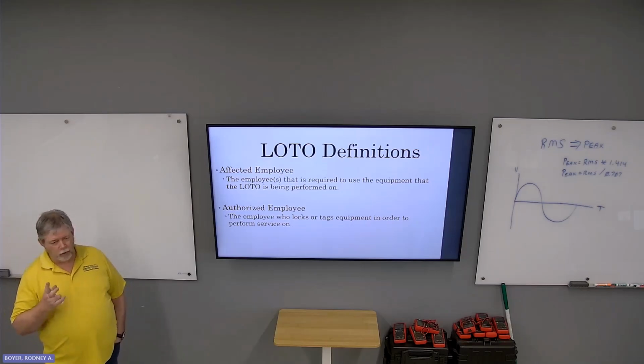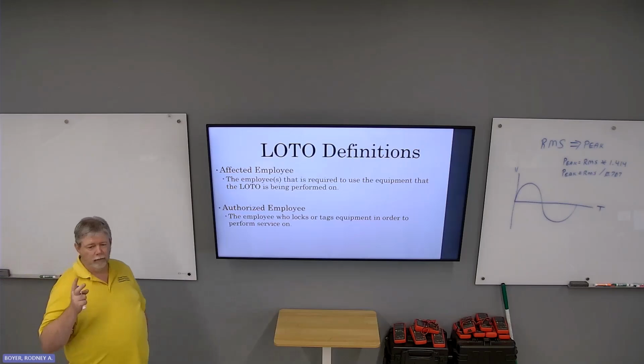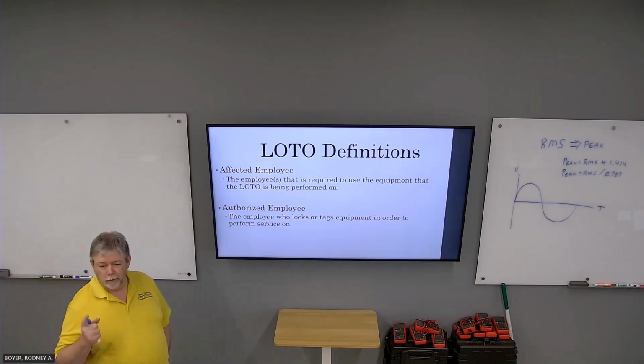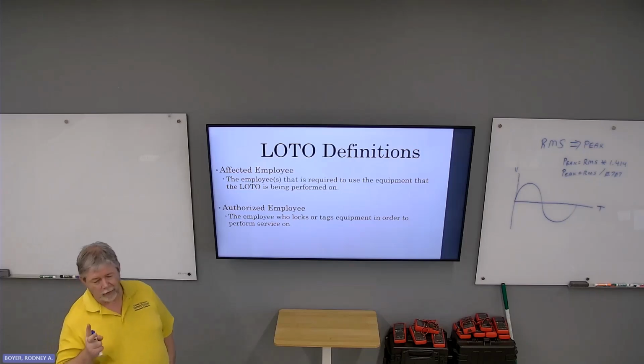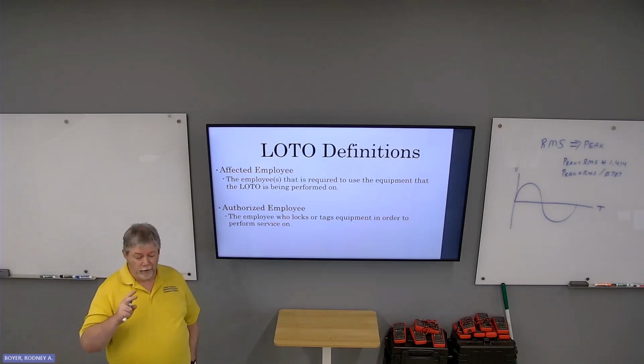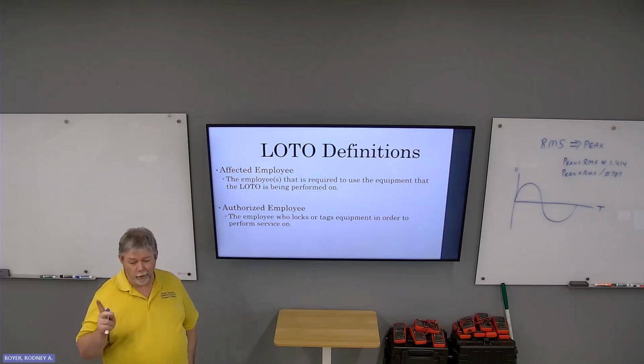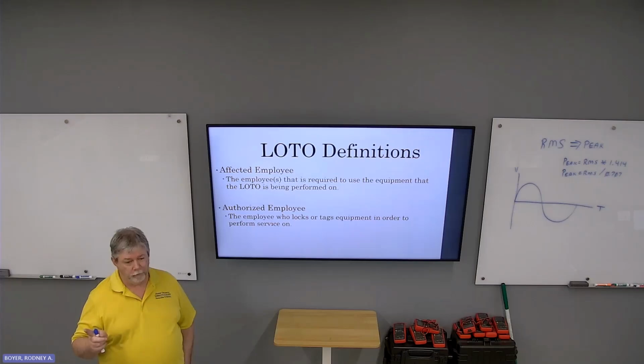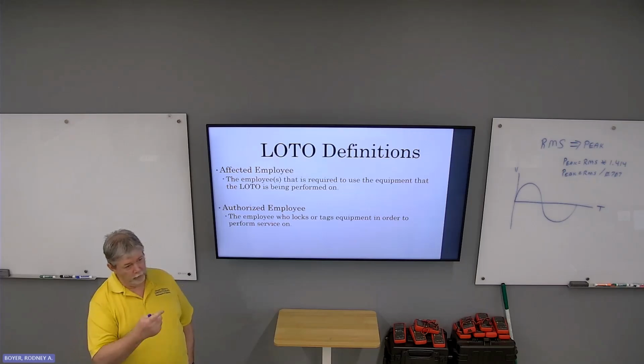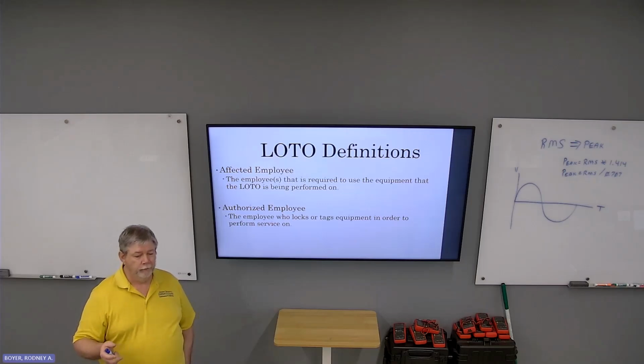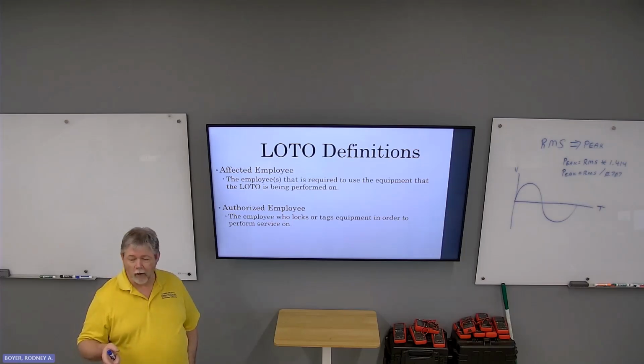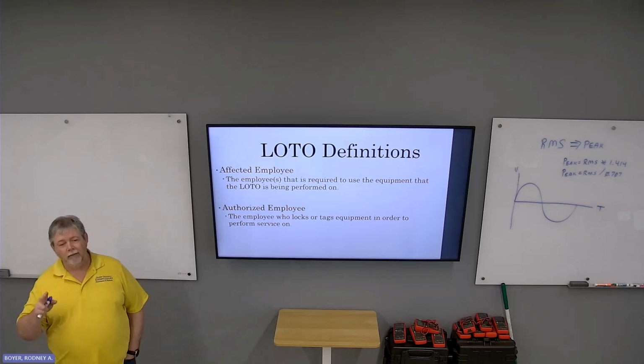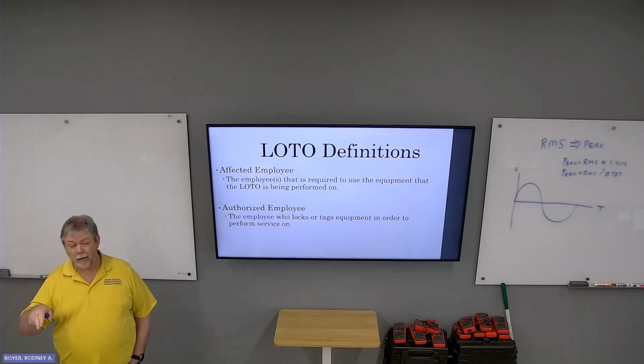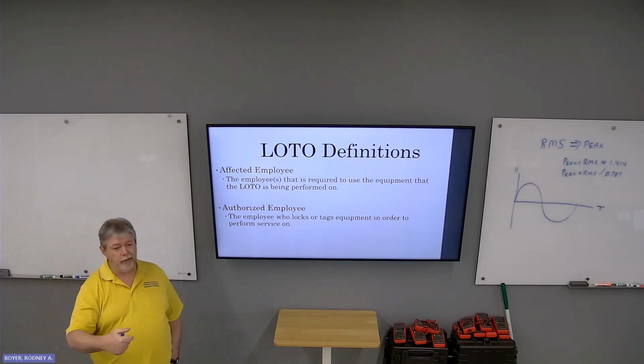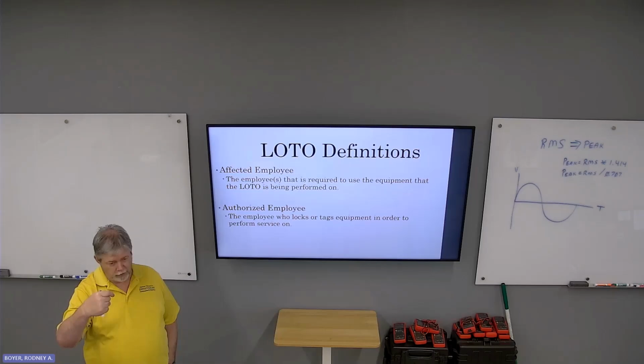There are only two people on the planet who can take a lockout lock off: the person who put it on, and their supervisor. The supervisor is only allowed to do it if the person who put it on is dead. You put your lock on, and on your way home you get hit by a bus - probably a grim day - and then your supervisor can take the lock off. The only other time is if you leave and forget to take your lock off; the supervisor has to contact you and get your verbal permission.